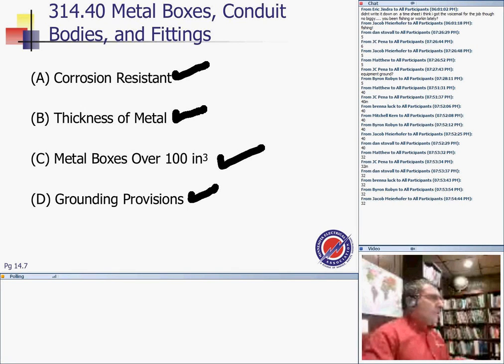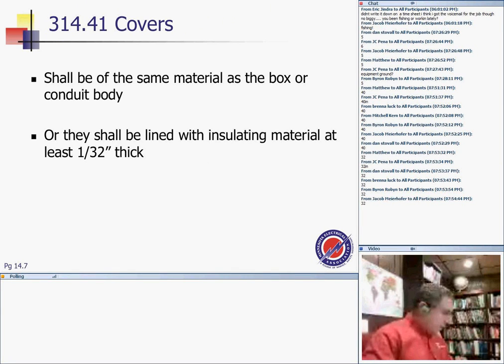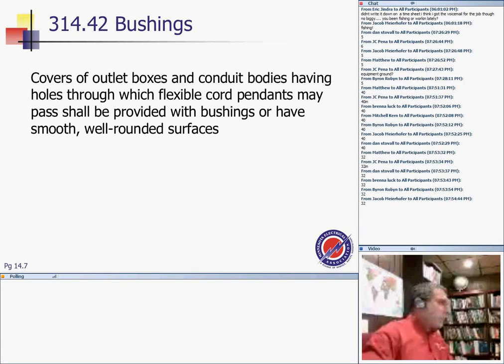So basically, in terms of grounding and a couple of other things, covers, 314.41. It says metallic boxes shall be of the same material as the box or conduit bodies with which they are used, or shall be lined with firmly attached insulating material that is not less than 1/32 inch thick, or they shall be listed for the purpose. So it's the same material as the boxes: metallic, non-metallic.